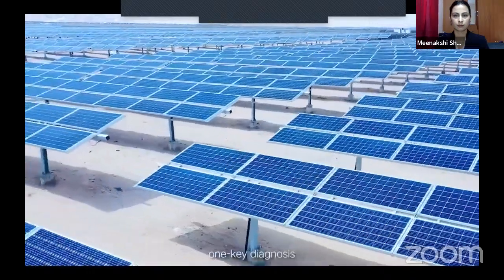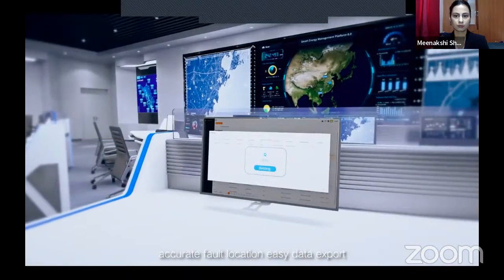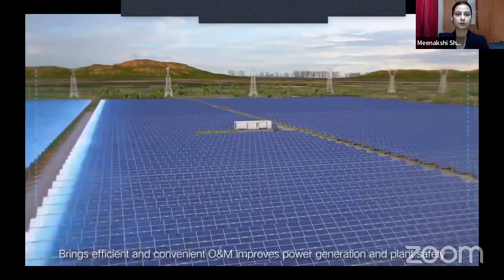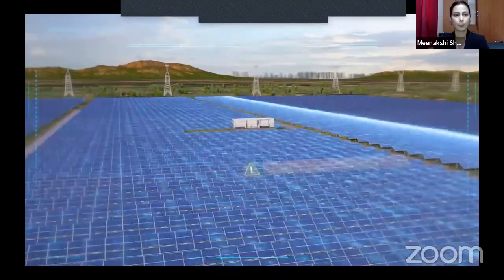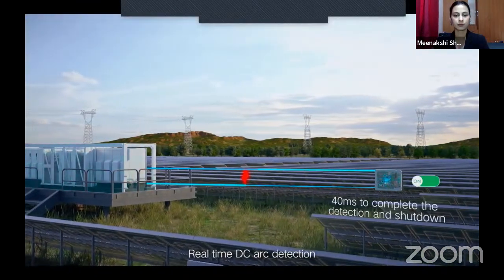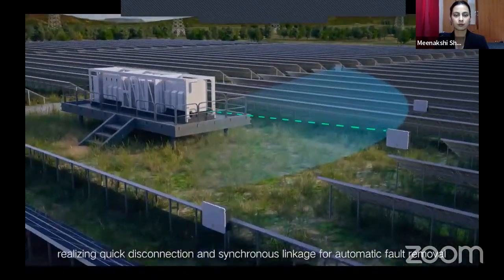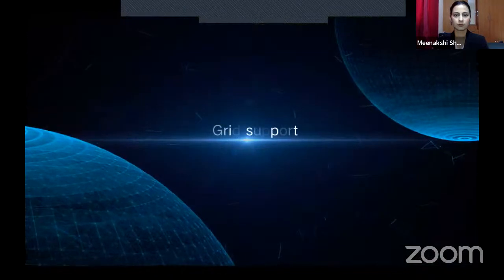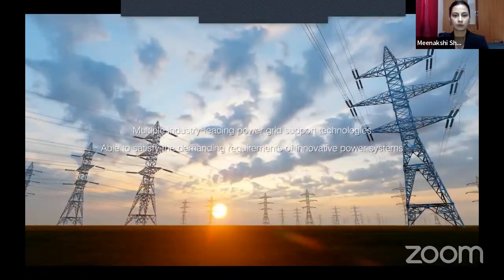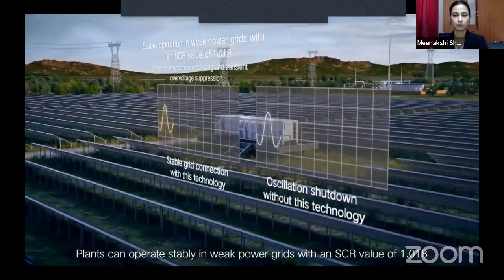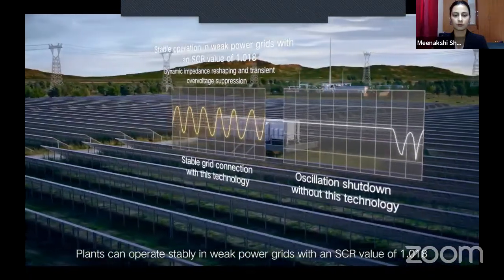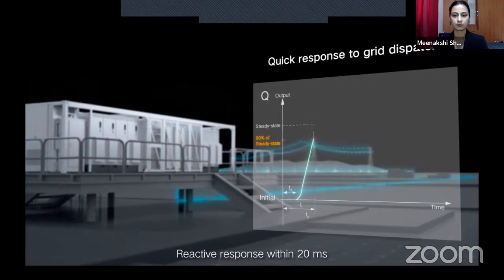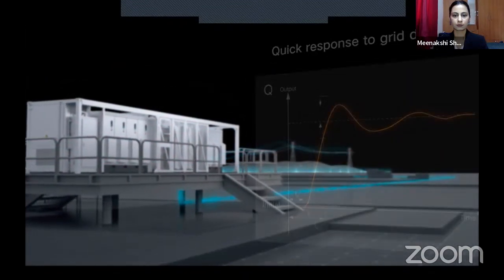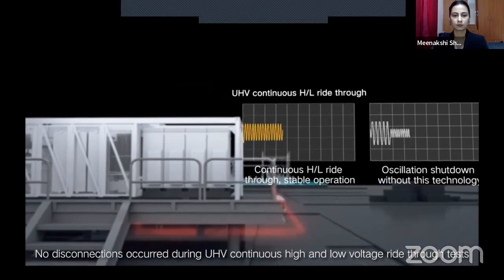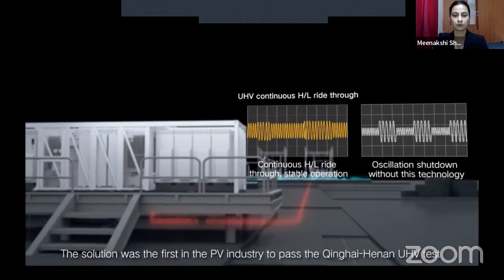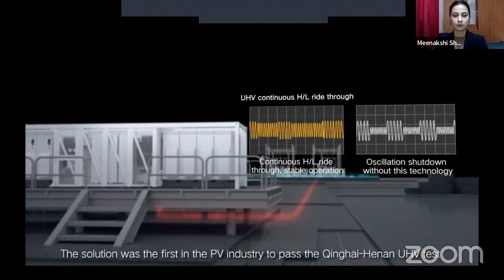Intelligent IV scan. One key diagnosis. Accurate fault location. Easy data export. Brings efficient and convenient O&M, improves power generation and plant safety. Real-time DC arc detection, realizing quick disconnection and synchronous linkage for automatic fault removal. Plants can operate stably in weak power grids with an SCR value of 1.018. Reactive response within 20 milliseconds, far shorter than required in national grid codes. No disconnections occurred during UHV continuous high and low voltage ride-through tests. The solution was the first in the PV industry to pass the Qinghai-Henan UHV tests.